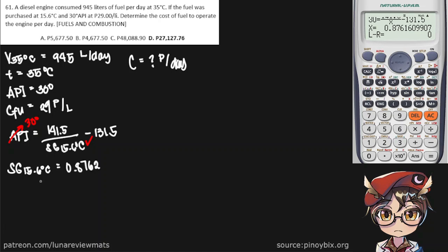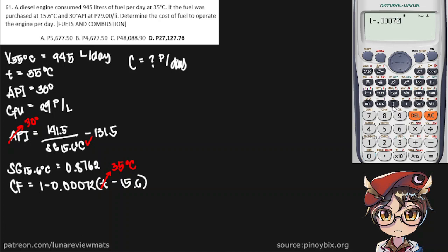We also need the specific gravity of our fuel at 35°C, so we need to use the correction factor formula. Please note that this correction factor formula only applies for temperatures in degrees Celsius. Our temperature T here is 35°C. Putting that into the calculator, we get a correction factor of 0.986.